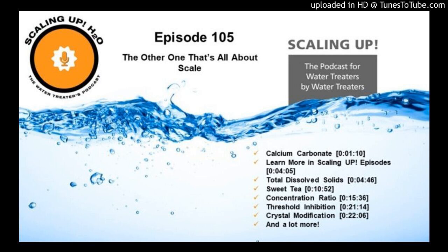So what we can do is add an agent that, when it comes out of solution, will distort what that crystal comes out as naturally. So instead of a box, it's now going to be a sphere or something distorted that kind of looks like a sphere, so it rolls around more instead of stacking. That's called crystal modification. Now, the last thing in our scale inhibition bag of tricks is dispersion.